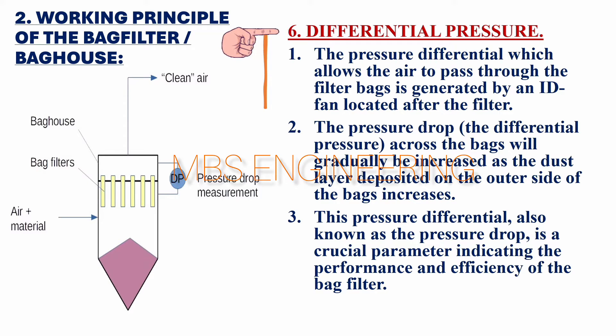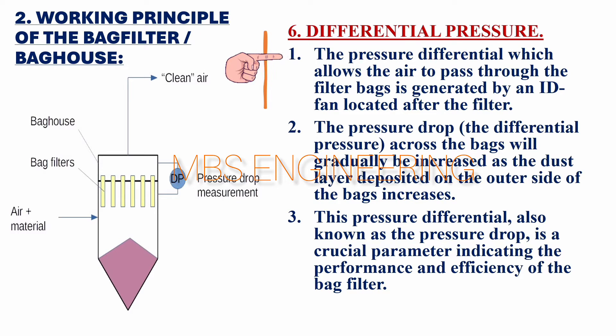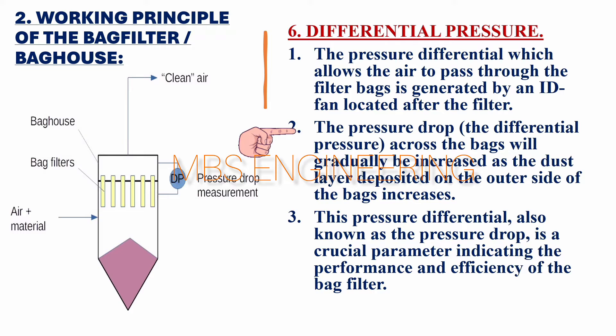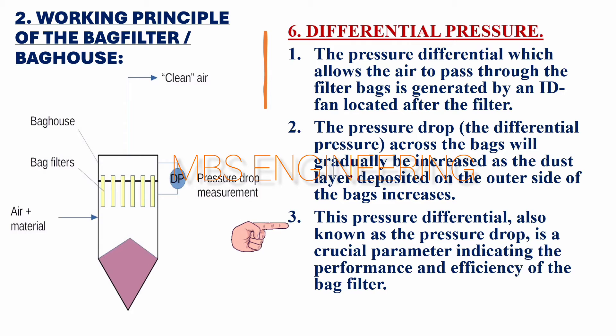Step 6 — Differential Pressure: The pressure differential which allows air to pass through the filter bags is generated by an ID fan located after the filter. The pressure drop across the bags gradually increases as the dust layer deposited on the outer side of the bags increases. This pressure differential, also known as the pressure drop, is a crucial parameter indicating the performance and efficiency of the bag filter.